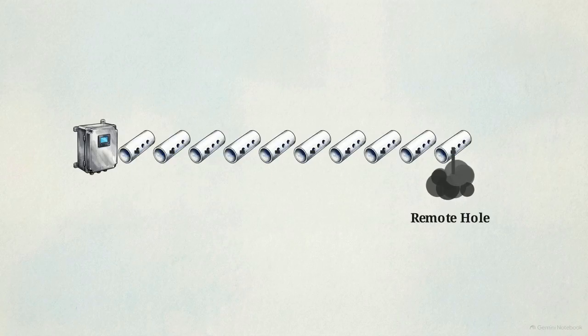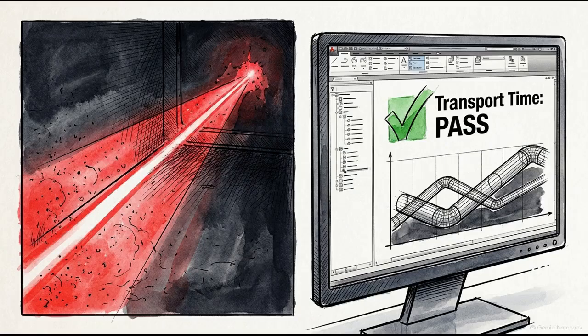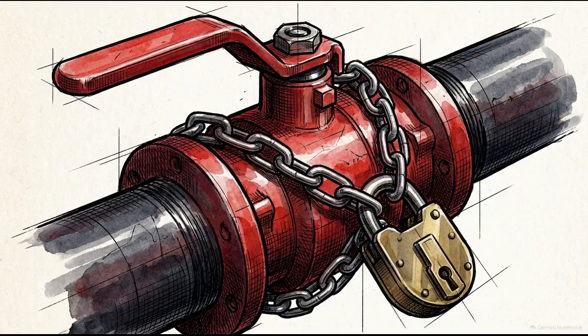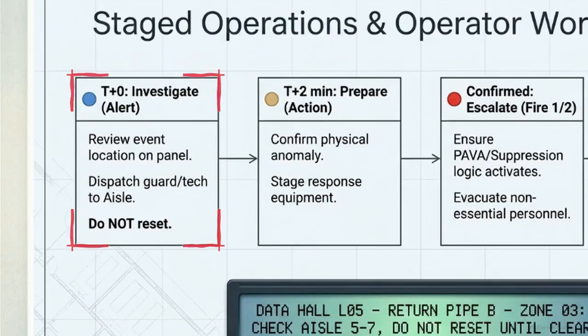Smoke entering one remote hole is heavily diluted by clean air entering all other holes on the pipe network before it reaches the sensor. A detector's high sensitivity rating provides no protection unless the hydraulic math proves that smoke from the furthest hole reaches the chamber, despite this dilution. Hypersensitive detection requires structural restraint to ensure that a localized smoldering wire does not trigger an immediate, unverified discharge of suppression agents. The response follows a staged workflow.